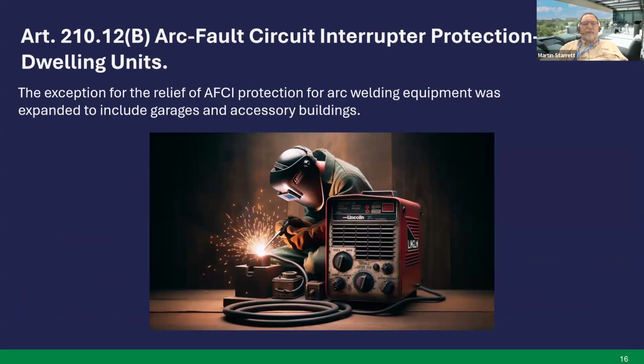Article 210.12(B), arc fault circuit interrupter protection for dwelling units. Again, there were no new arc fault circuit interrupter requirements added. What we've had in the 2023 will currently stand. But in (B), they did add an exception, and the relief of AFCI protection for arc welding equipment was expanded to include garages and accessory buildings. So there were no new requirements added to dwelling units beyond what we already have.